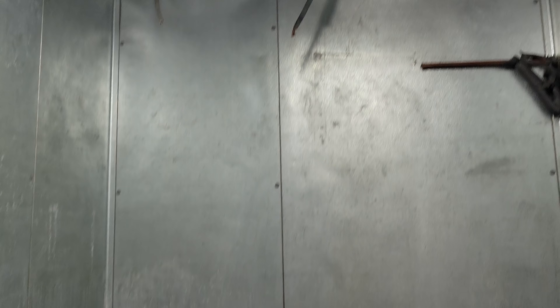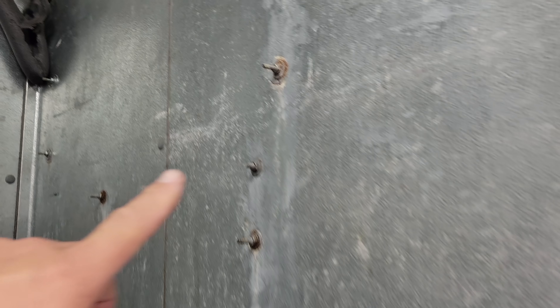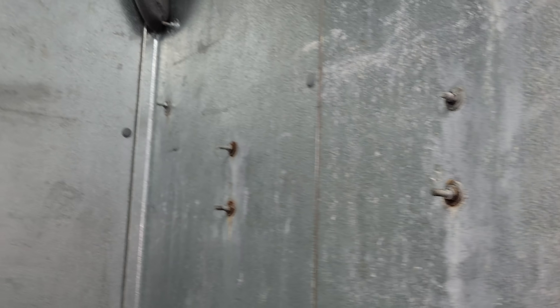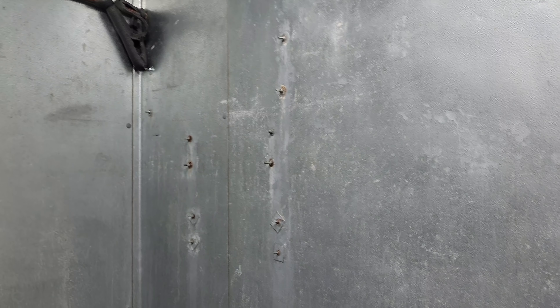They need to fix the electrical issues. They've got to figure all this stuff out. I don't know if the code inspector is going to be okay with that grout — they're going to have to have it cleaned because they're going to treat this as a new install. The code inspector is not going to like the galvanized, rusted bolts. The health department is going to want it all to be stainless. Yeah, this is a giant mess.